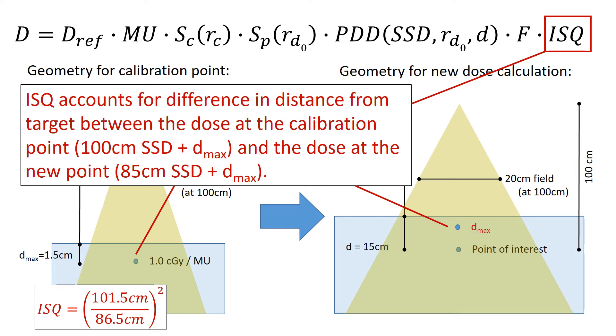And so our inverse square correction is going to be 101.5 cm divided by 86.5 cm squared. And that's basically just taking the dose difference due to the inverse square law, going from that point that's farther away that we started at, the calibration point, to our new normalization point.